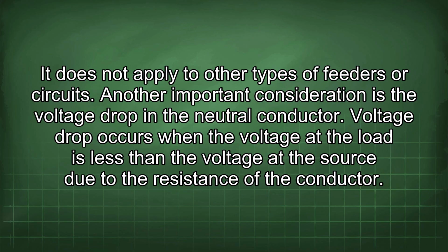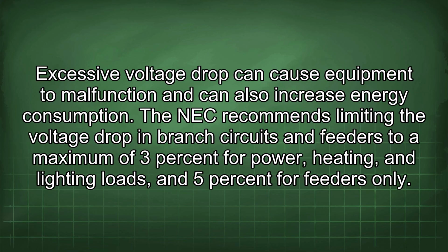Another important consideration is the voltage drop in the neutral conductor. Voltage drop occurs when the voltage of the load is less than the voltage of the source due to the resistance of the conductor. Excessive voltage drop can cause equipment to malfunction and can also increase energy consumption.